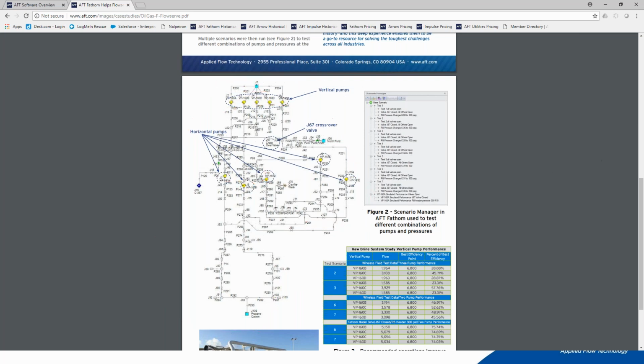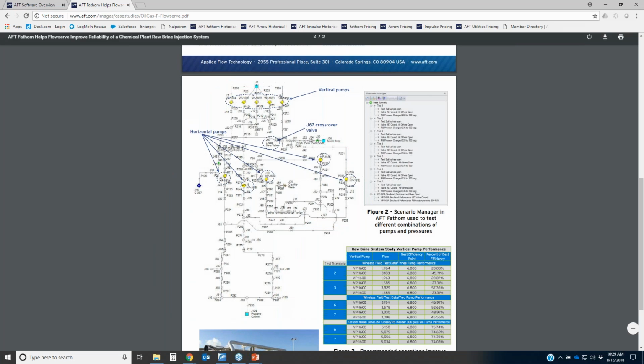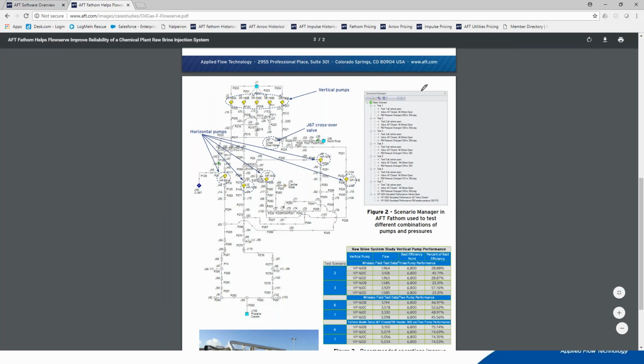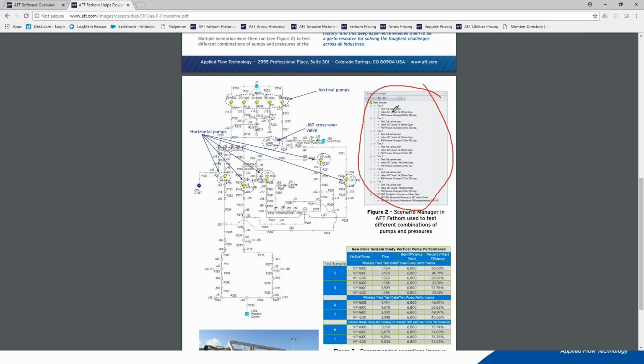As Flowserve began their analysis, they ran some test cases. They made very good usage of the scenario manager right here, where they model all their individual cases like this. And what they found was the pumps that were operating very far away from their best efficiency point. Look at that. For cases 2 and 3, they had pumps that were operating at as low as 23% of their best efficiency point. So flow being choked back way, way low.